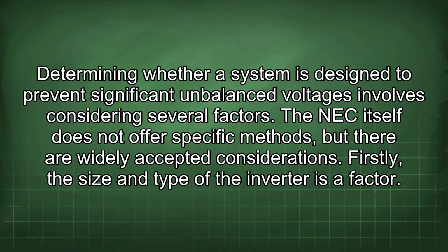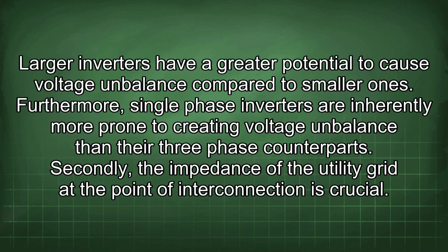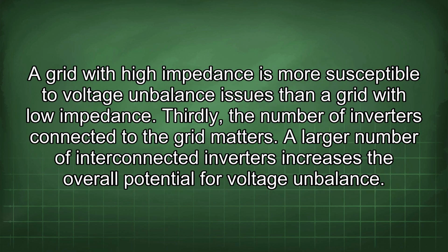The NEC itself does not offer specific methods, but there are widely accepted considerations. Firstly, the size and type of the inverter is a factor. Larger inverters have a greater potential to cause voltage unbalance compared to smaller ones. Furthermore, single-phase inverters are inherently more prone to creating voltage unbalance than their three-phase counterparts. Secondly, the impedance of the utility grid at the point of interconnection is crucial. A grid with high impedance is more susceptible to voltage unbalance issues than a grid with low impedance.